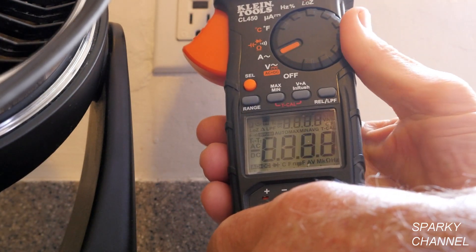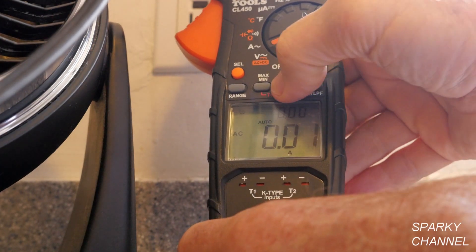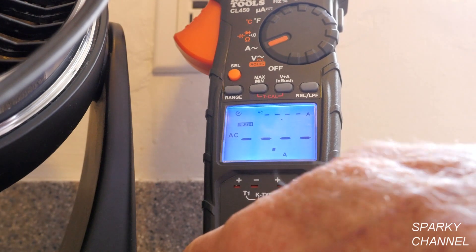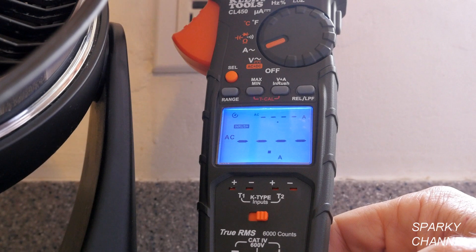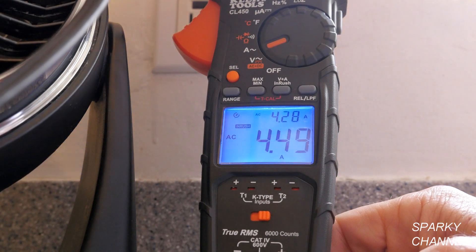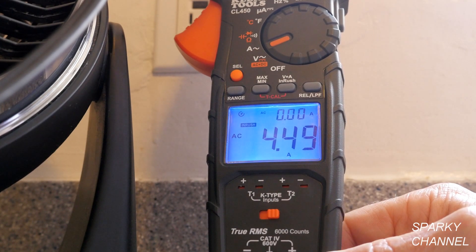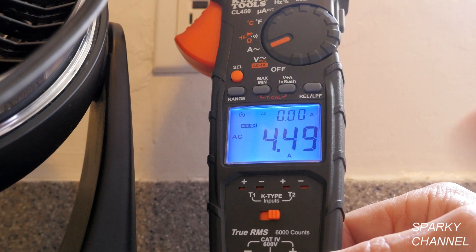Now I'll show you the inrush feature. We'll put it back on amperage and select V plus A inrush — long-press it for two seconds. Turn the backlight back on. This gives you the starting amperage. Turning the fan on to speed one, the startup amperage is 4.49 amps. Startup amperage is higher than running amperage, and measuring it is an important diagnostic feature.